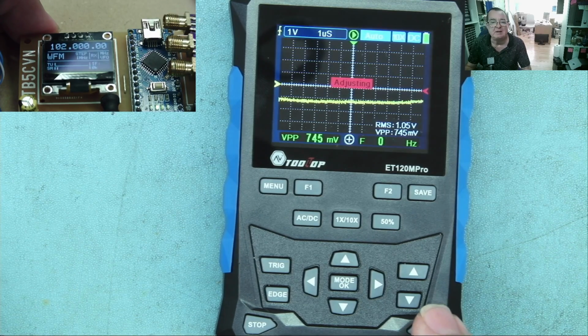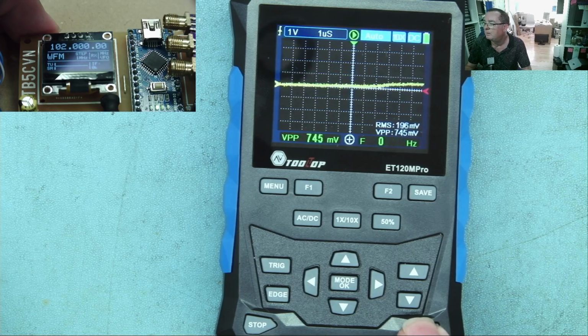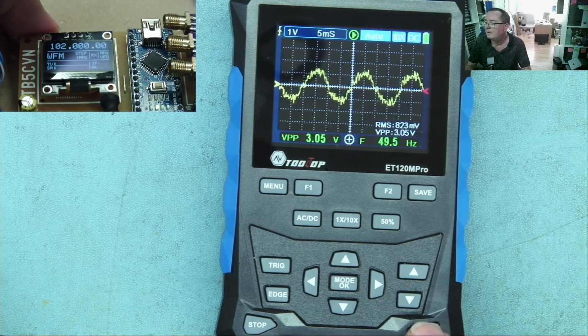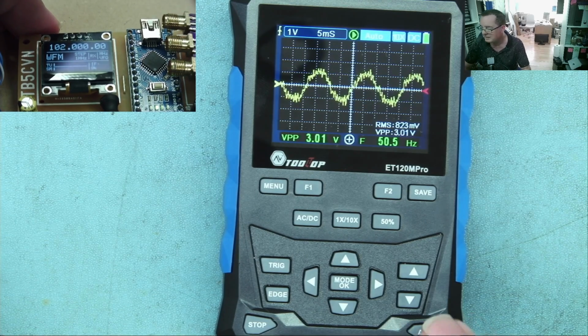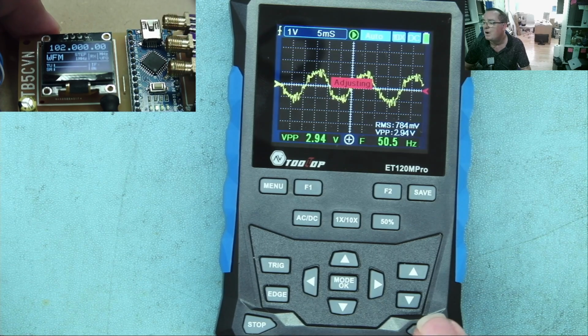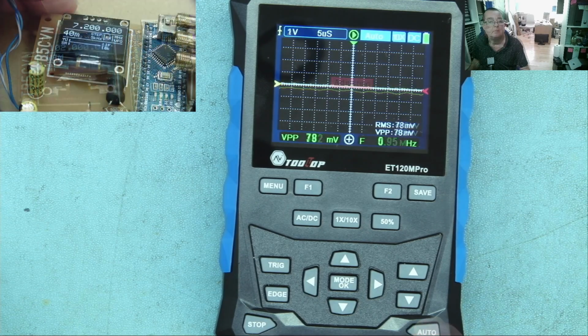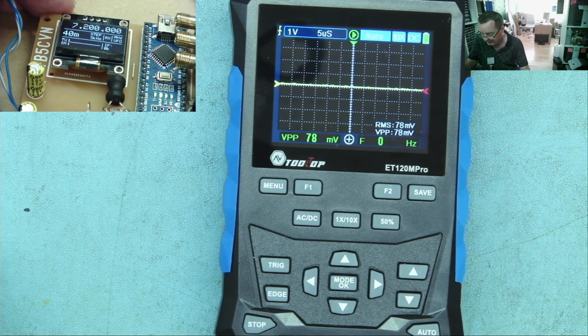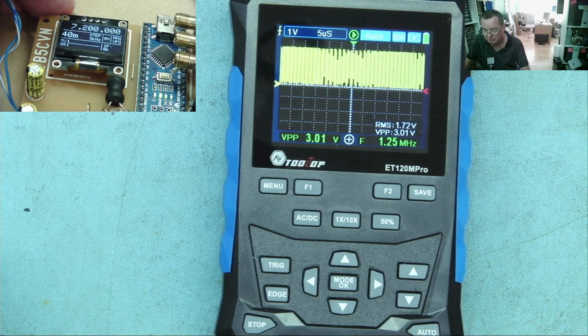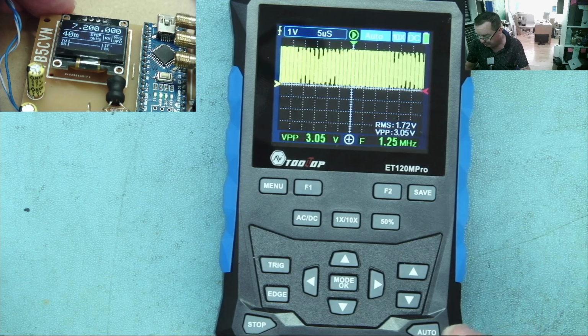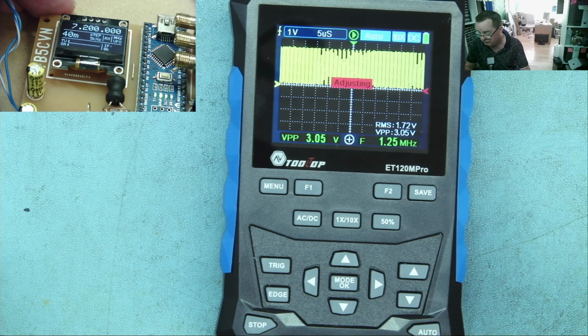Well, to be quite honest, that's a nasty waveform. And it's got it, but it thinks it's 50 hertz. That might be the low frequency component it's actually seeing in the signal. I said there was a lot of noise in this signal at mains frequency. I've tried to correct the grounding of the probe. So let's have another look.